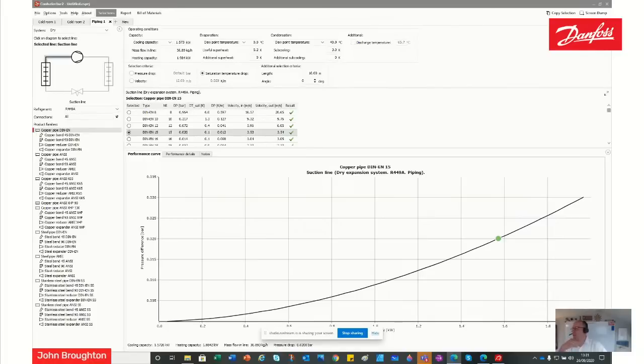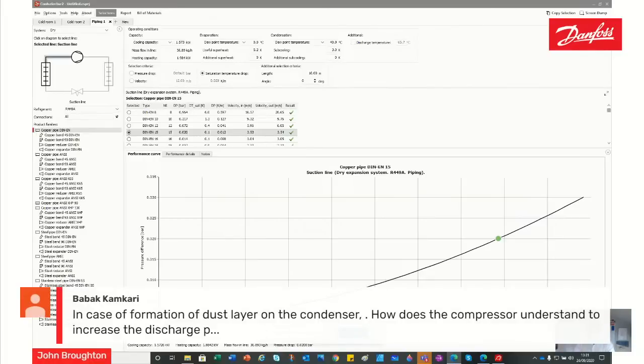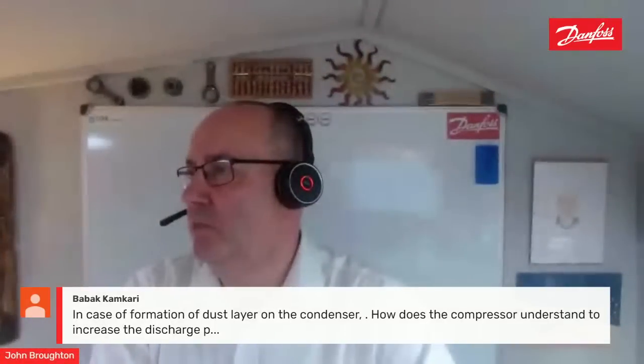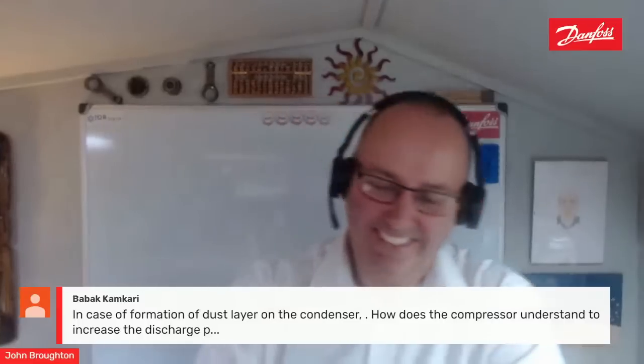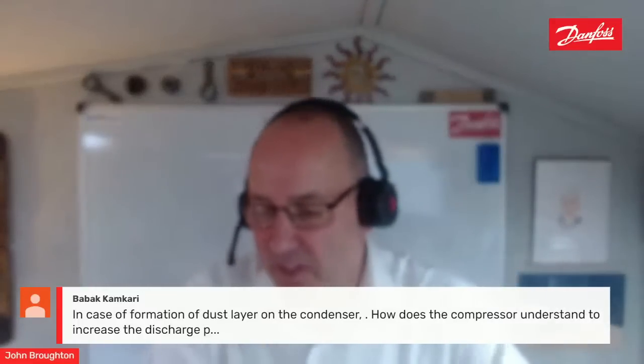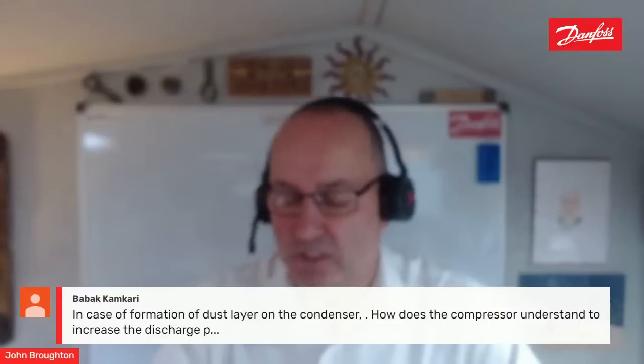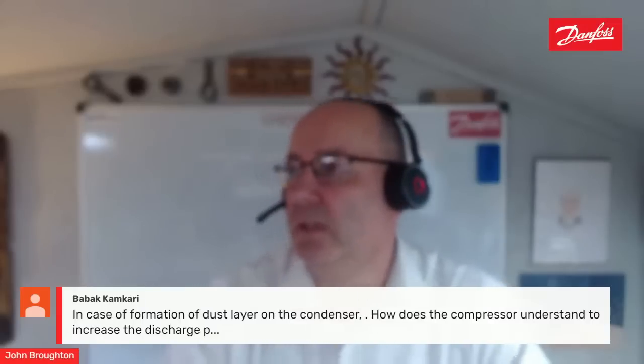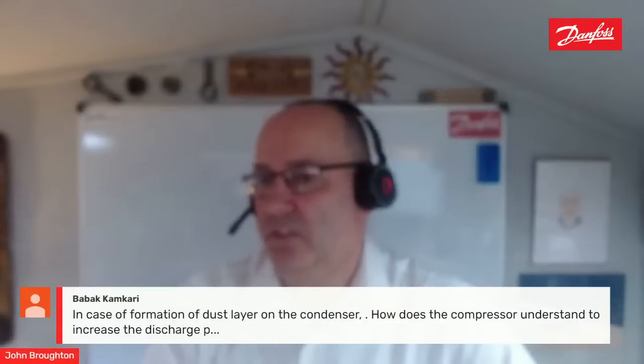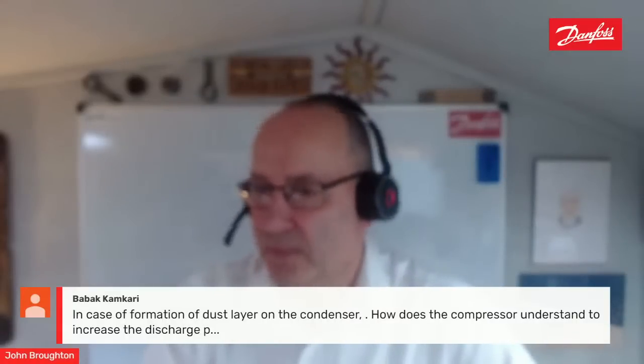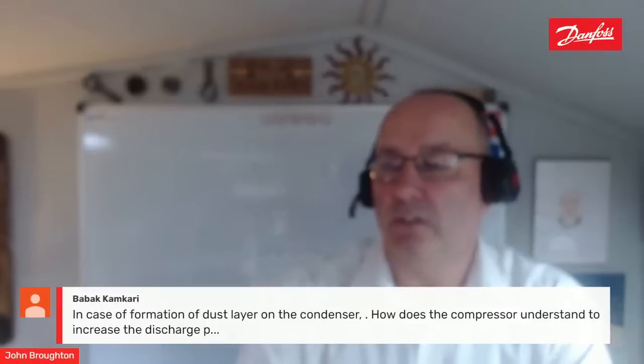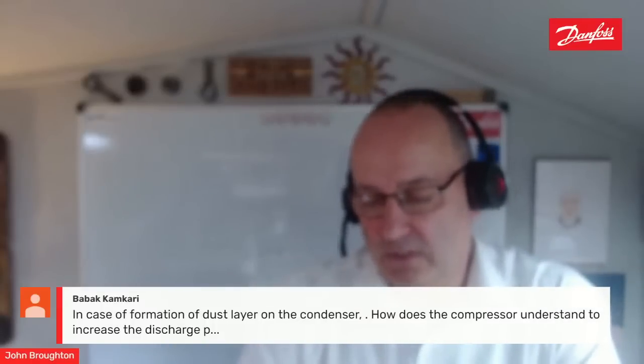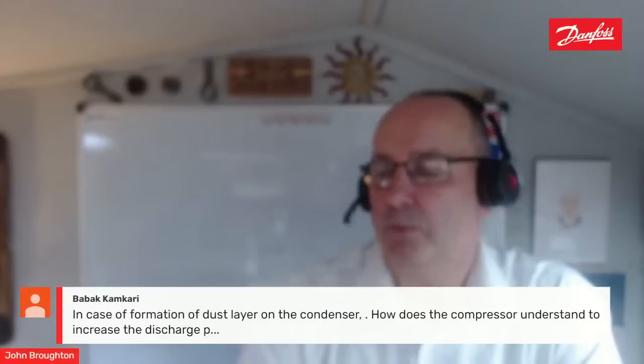Babak asks, in case of formation of a dust layer on the condenser, how does the compressor understand to increase the discharge pressure in practice? Basically, if the condenser is blocked or is getting blocked, the discharge pressure will increase naturally because we're not condensing enough. That's the simplest answer, really. A dirty, blocked condenser is one of the biggest challenges with compressor operation generally.